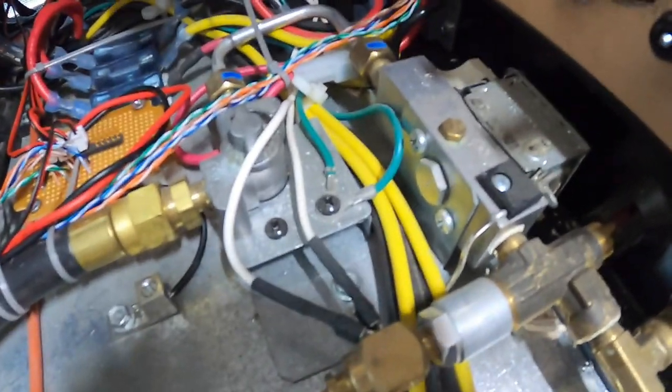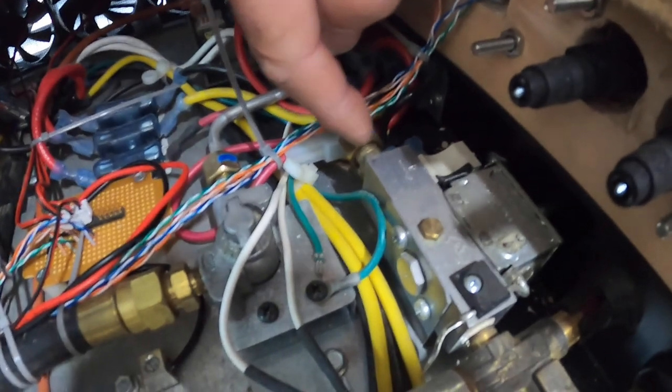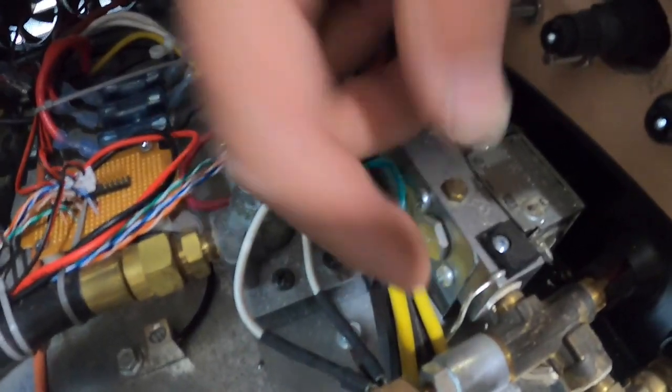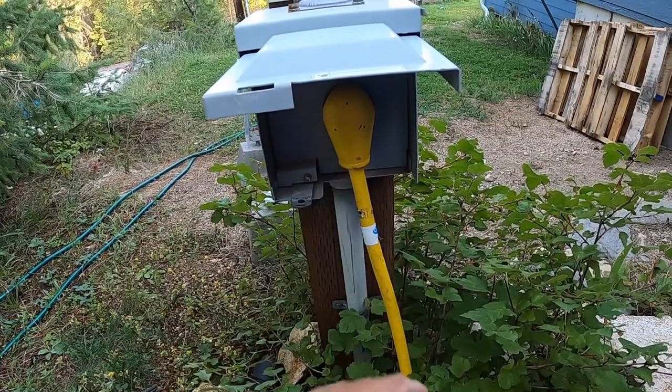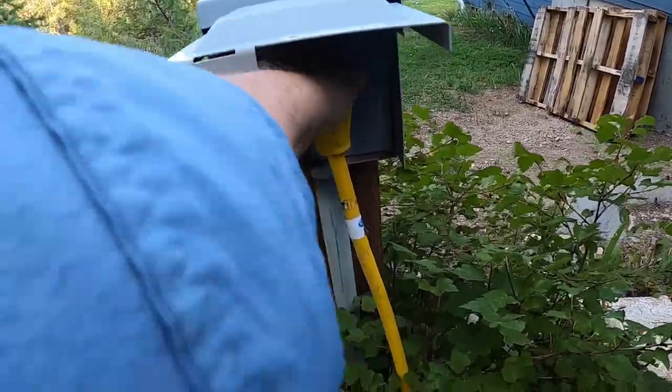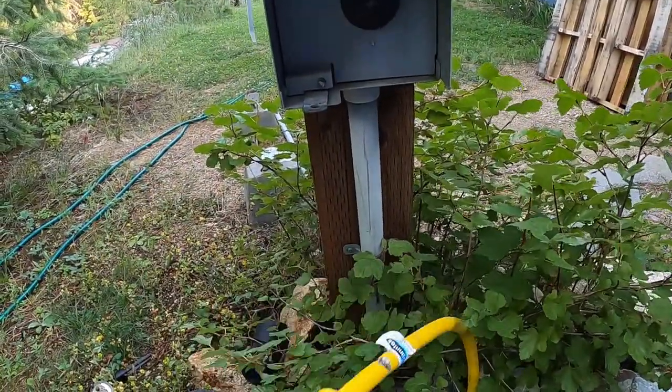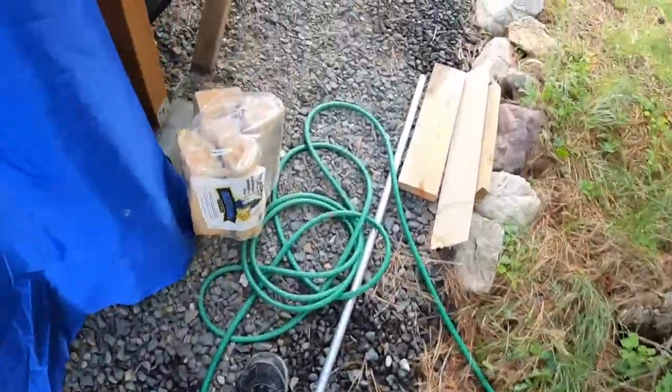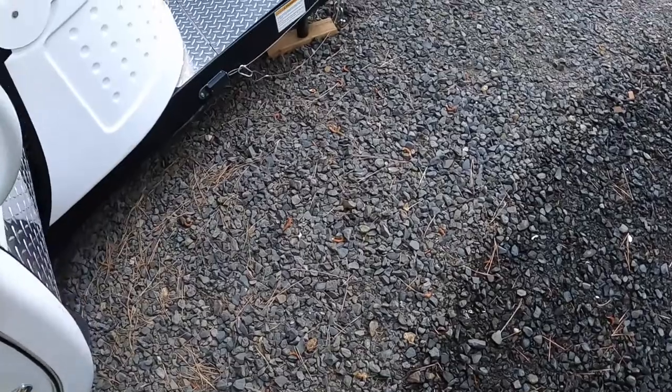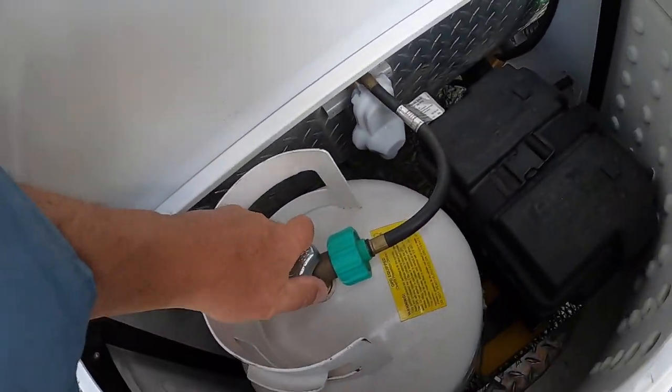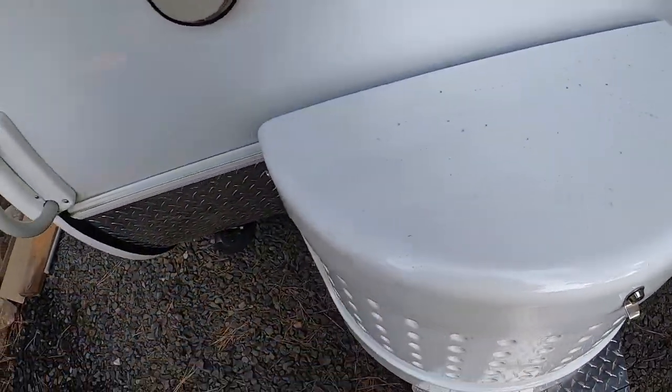I'm not going to pull wrenches out here and show you that. It's pretty straightforward. It's just the input line, the output lines, and these two screws. And then this guy lifts out. And you just pull that sensor out. So let's get out of here for your own safety before you start working on this guy. You need to unplug from street power. Don't want to get shocked. Next thing you want to do, you want to turn your gas off. Don't want to have any gas leaks.